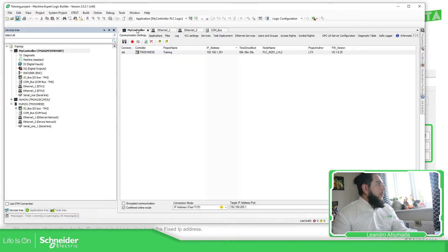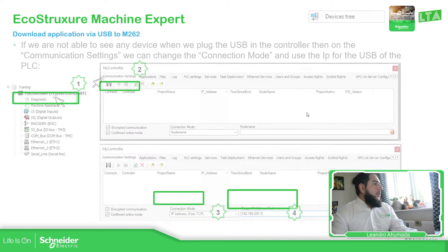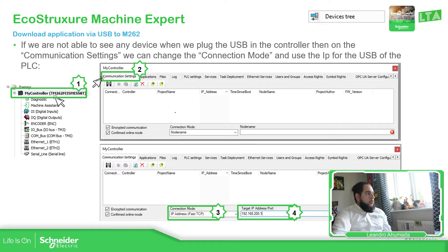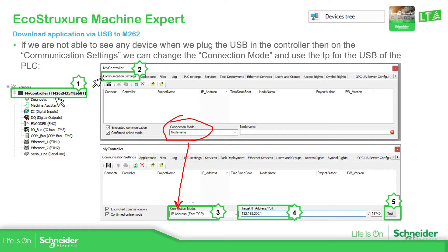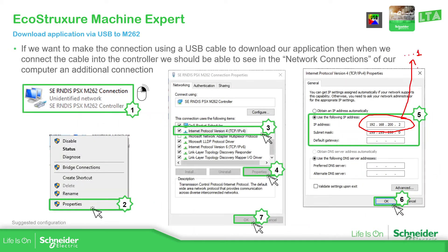I'm going to save this and then go to my controller. So we have the possibility to change the IP address of our port, and after downloading via USB, we can connect using the Ethernet port. If we want to make the communication and we don't see the controller on the list — which is the same situation I have — we just need to go to My Controller and change the connection mode. Let me change the view to IP Address Fast TCP, and then use the default IP address for the USB port. If we add this, we should be able to add our controller on the list.